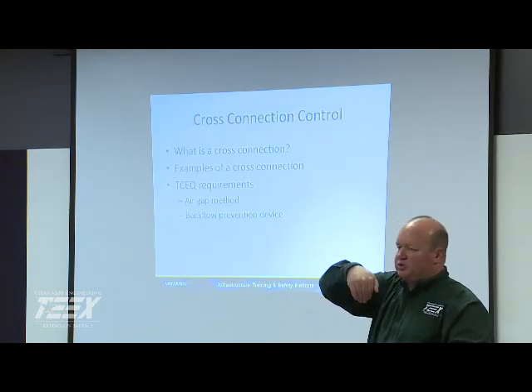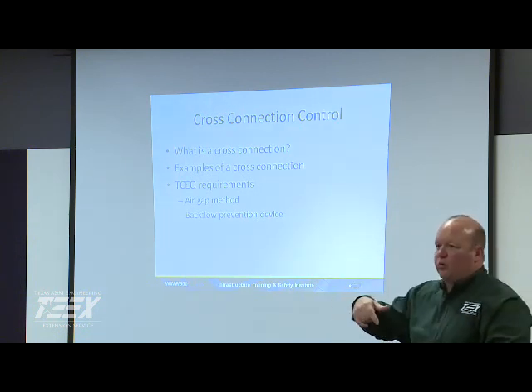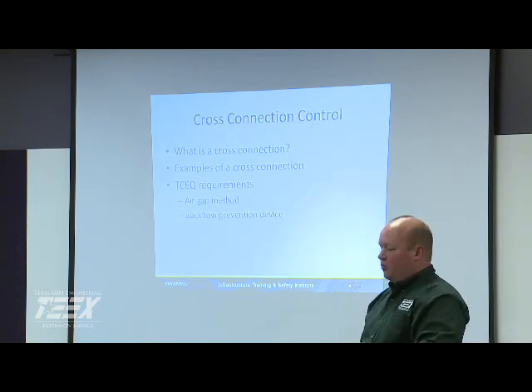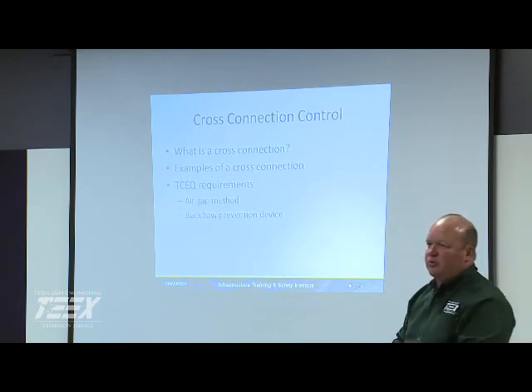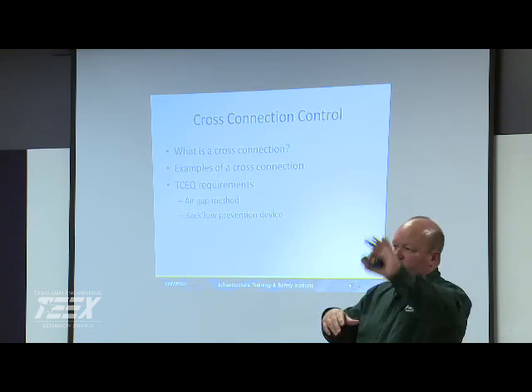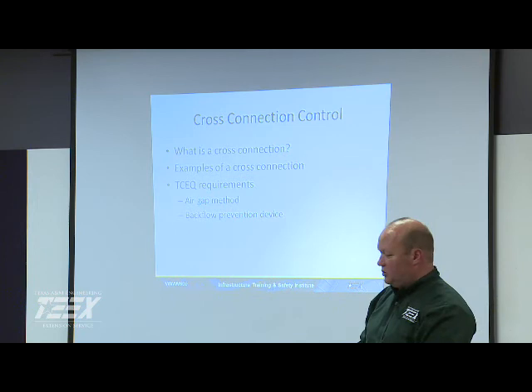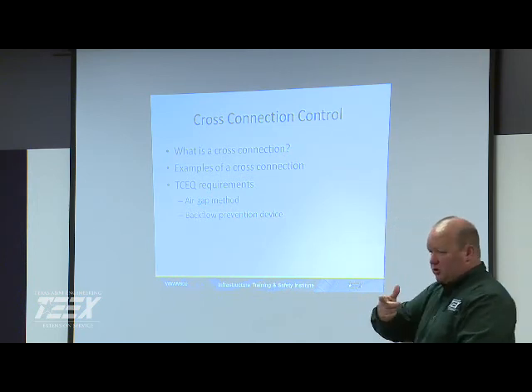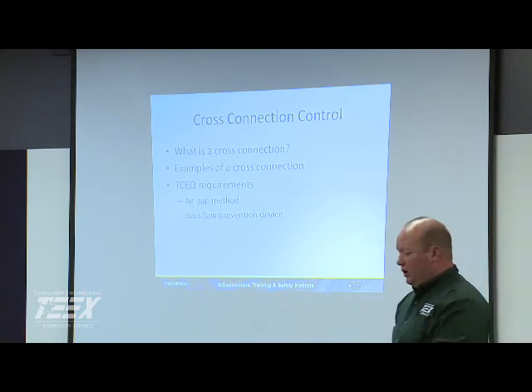Yeah. We had a big gooseneck coming off of our backwash, and the backwash recycled water would actually go up through an air gap. That was probably a 36-inch pipe and a gooseneck. It was pretty cool. It was a nice air gap so that you didn't have any back siphon coming from your backwash. So a lot of it depends on the age of the plant and how it was designed, especially on your turbidity meters and stuff like that. A lot of times they'll have an air gap set up in it.